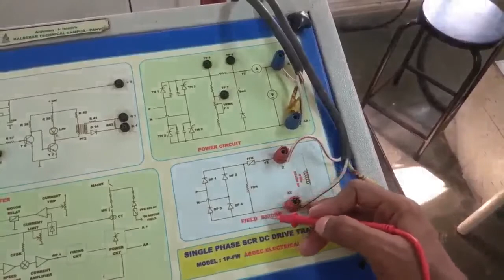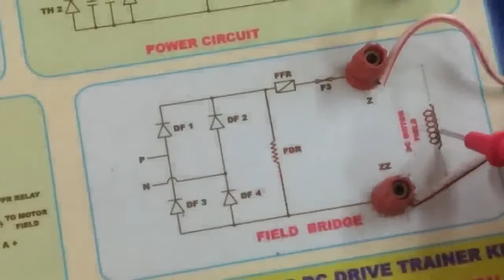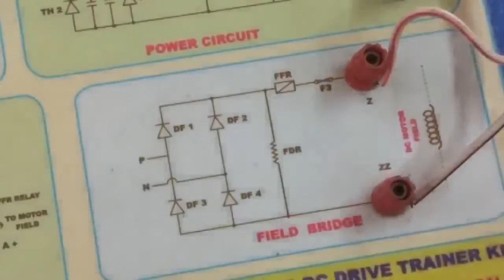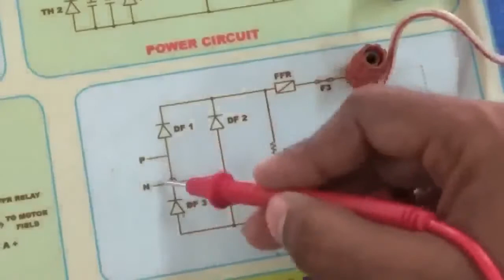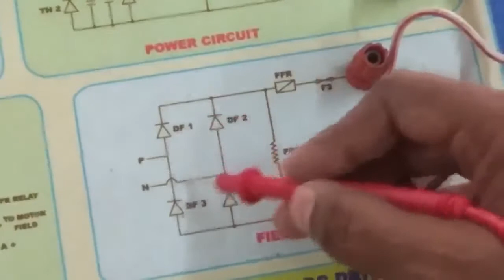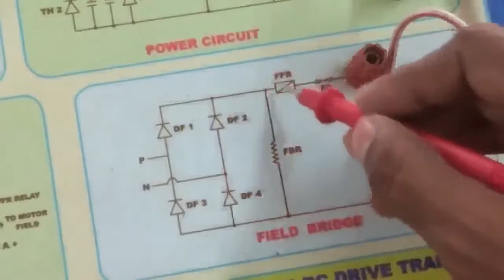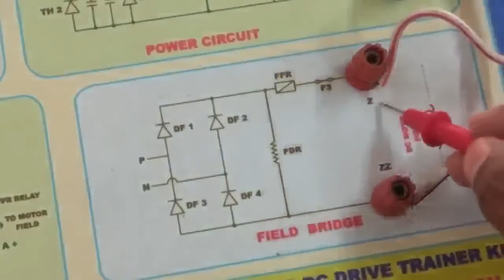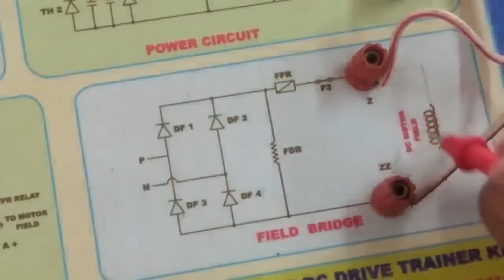And this section is the field bridge or field circuit, you can see here clearly. In this circuit, we are separately exciting the field winding. I have already connected the field winding terminal of the motor to the kit here in the field bridge section. In this field circuit section, we are giving the AC supply to this bridge circuit, a diode rectifier bridge circuit, and the output of this bridge circuit, the DC supply, we are giving to the field winding terminals Z and double Z. This is the separately excited connection of the field winding.